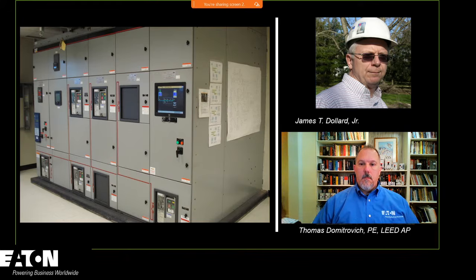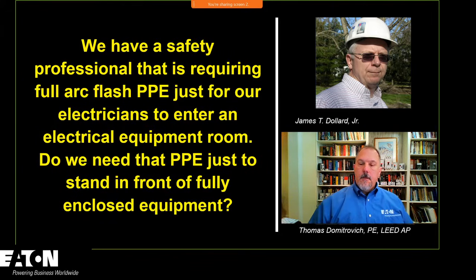And if you go back to that question, there is no arc flash hazard, because they may simply be going into that electrical room, that electrical area, to take a look at a panel schedule or other. If we were to agree with this safety professional that you needed PPE to go into an electrical equipment room, think of all the office spaces where we've got a panelboard in a hallway. Yeah. That means everybody working in that facility, when they walk down the hallway, would have to be decked out in Category 1 or Category 2. It's just not feasible. Yep. And it's not necessary.